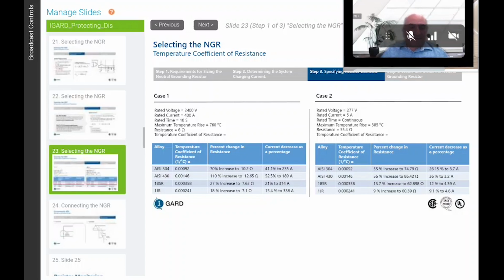So at the end of a 760 degrees C temperature change, your resistance from a 6 ohm resistor changes to 10.2 ohms for 304. It more than doubles for 430, and your current changes correspondingly from 400 amps to 234 amps for 304, and from 400 amps to 189 amps for 430. This is the resistance element that we use. So we have a 7.1 increase, or 18% increase in resistance to 7.01, which decreases the current by 15.4%.